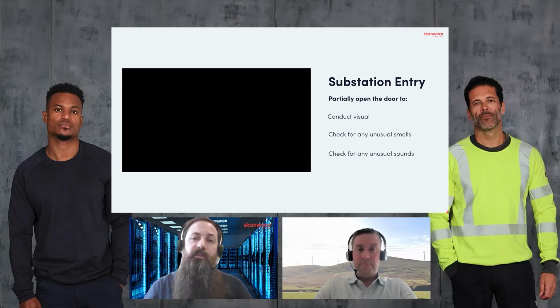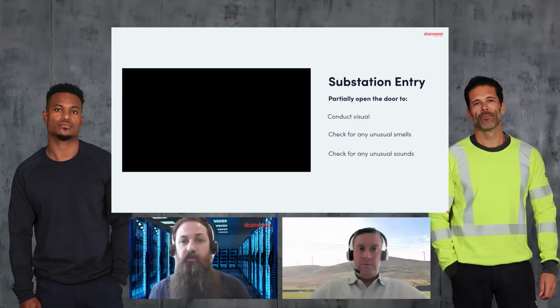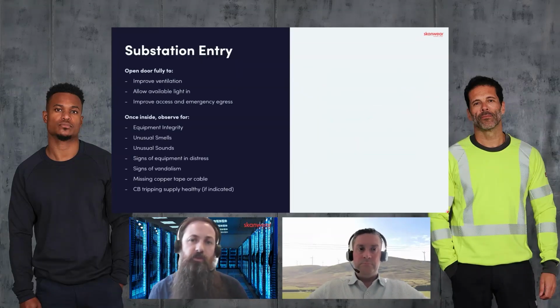Often, people with less training or experience who identify equipment or switchgear in distress try to operate it to make it safe, but that's not the recommendation. In that eventuality, if you open the door and hear indications of switchgear in distress, the correct process is to secure the substation, raise the alarm, and then in a steady process try to disconnect it from another means, from another place. That's what's gone on in the other video, and you can see the outcome, where the person interacted with the gear and it resulted in a flashover. Hopefully in most of your substations you wouldn't come across that.